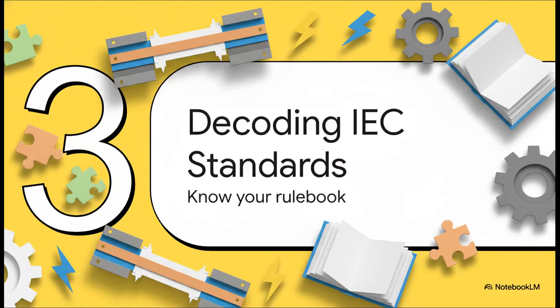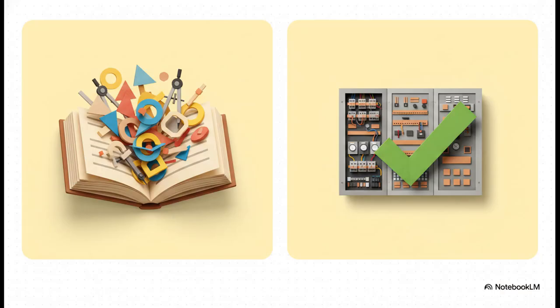Moving right along to Section 3, decoding the IEC standards. Now we've got to tackle the bureaucratic side of the design. Look, I know reading standards isn't exactly a weekend hobby, but we're going to de-jargon these documents right now because panel builders mix them up all the time. Over on the left is IEC 60664-1. This is the underlying insulation coordination standard. It gives you the actual math, the dimensioning logic, the altitude guidance. On the right, we have IEC 61439. This one governs the low-voltage switchgear as a finished product, detailing the construction rules and requiring routine verification.